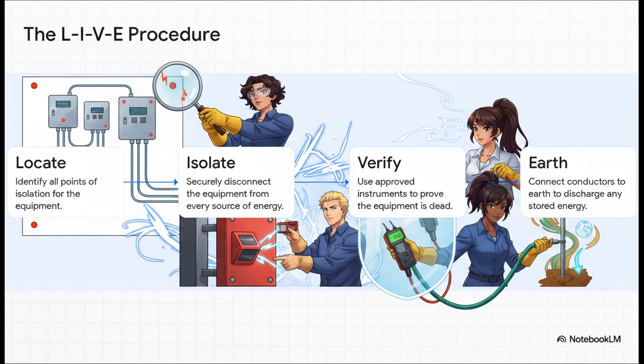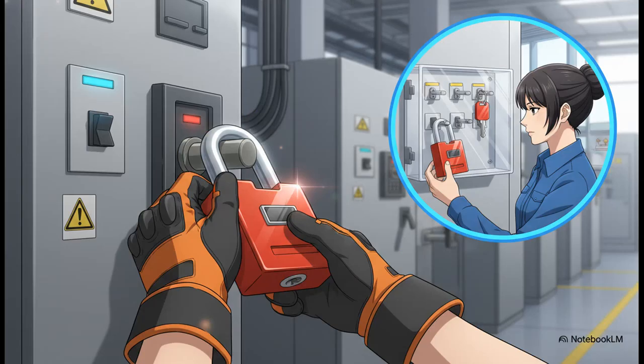Locate, isolate, verify, earth. You have to follow every step, in order. And when we say isolate, we don't just mean flipping a switch and walking away. We're talking about a secure, physical disconnection. This is usually done with safety locks that have unique keys, and those keys are then placed in a controlled key safe managed by the authorized person. This makes it physically impossible for someone to accidentally re-energize the equipment while you're working on it.